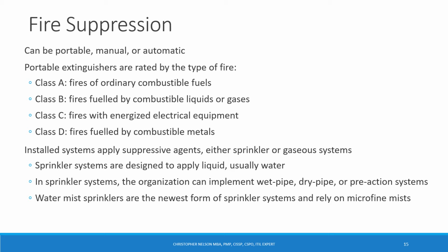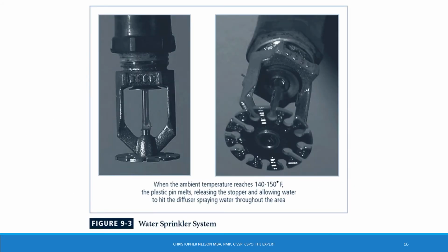For fire suppression, you can also have sprinkler systems, which apply liquid, usually water. Water mist sprinklers are the newest form of sprinkler systems and rely on microfine mist. In sprinkler systems, the organization can implement wet pipe, dry pipe, or pre-action systems. For a water sprinkler system, it is activated when the ambient temperature reaches 140 to 150 degrees Fahrenheit. The plastic pin melts, releasing the stopper and allowing water to hit the diffuser, spraying water throughout the area.